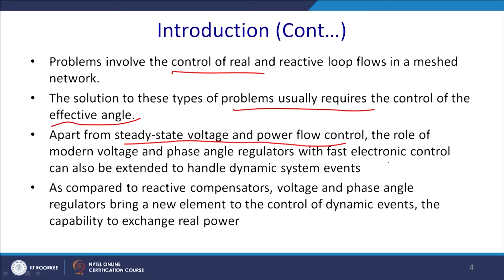Apart from steady state voltage and power control, the role of the modern phase angle regulator with a fast electronic control can also be extended to handle dynamic system events like oscillation, faults, subsynchronous resonance, all those. As compared with the reactive compensator, voltage and phase angle regulators bring a new element to the control of dynamic events, and the capability of power lines is enhanced. It is one of the new members, and it shows huge potential to effectively control the power handling capability of the transmission line.